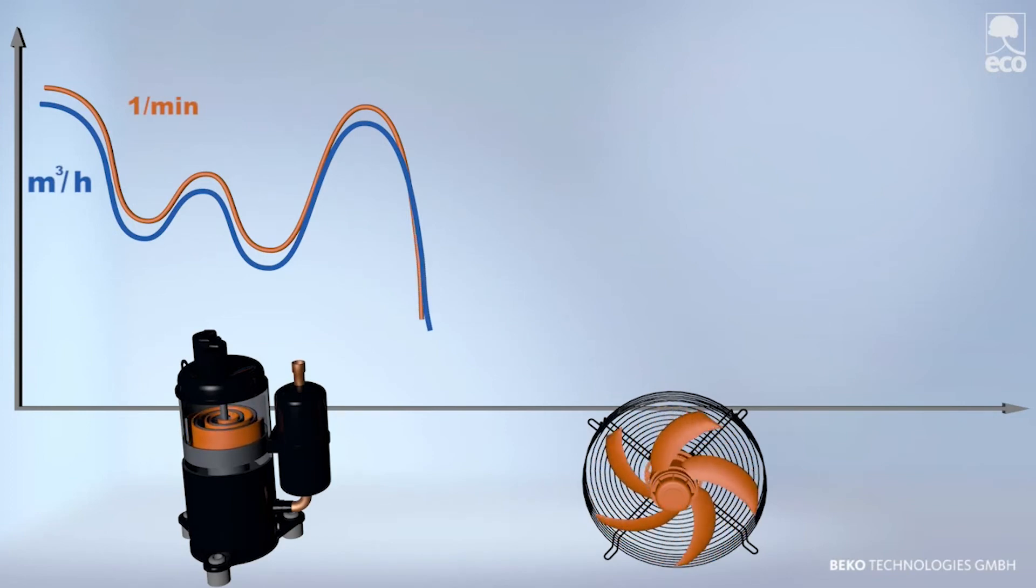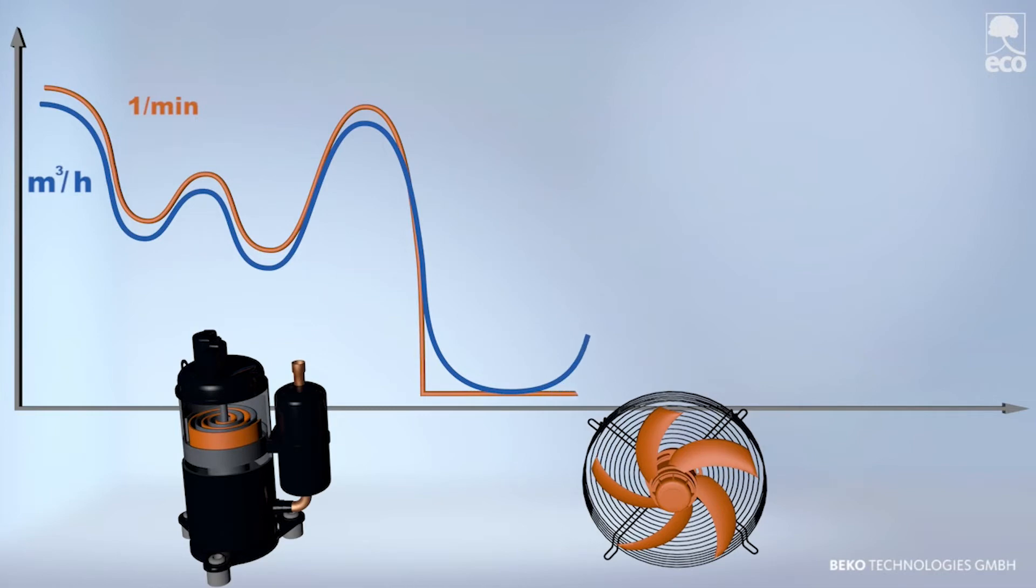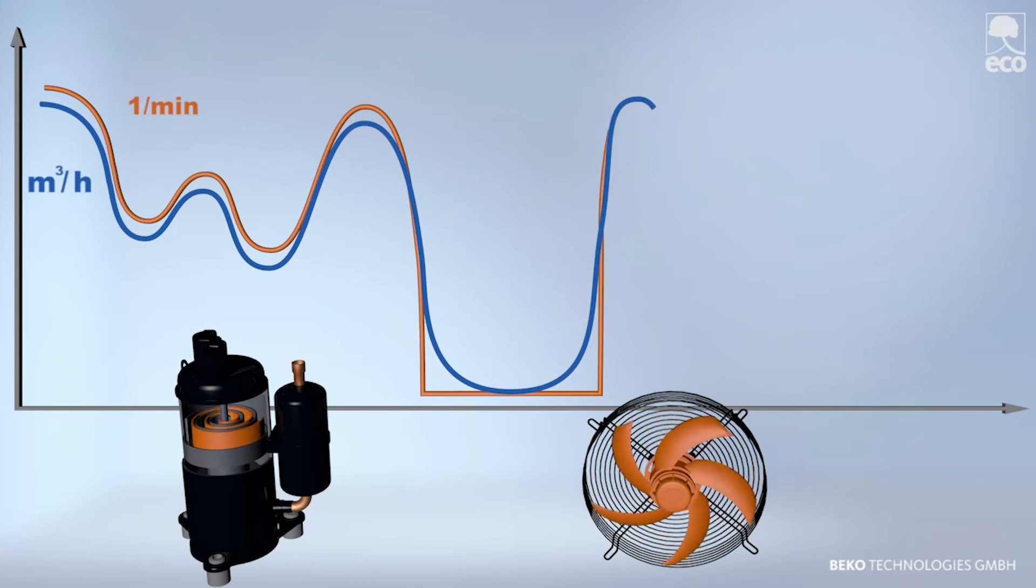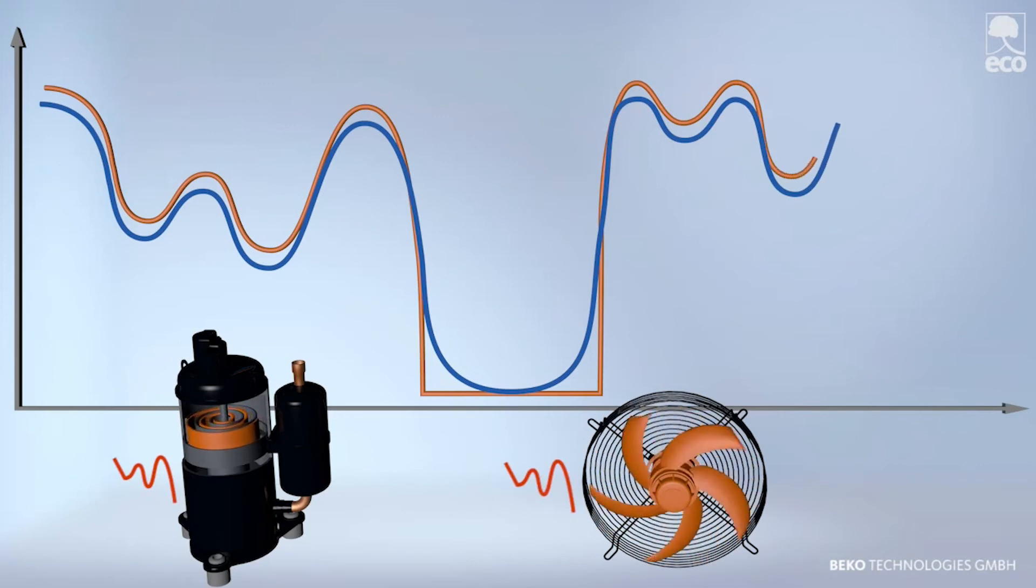After reaching a certain system size, the drying performance is controlled by changing the frequency of the compressor, and thus even more finely adjusted to the volume flow. Larger dryers adapt both the speeds of the compressor and the fan to match the volume flow.